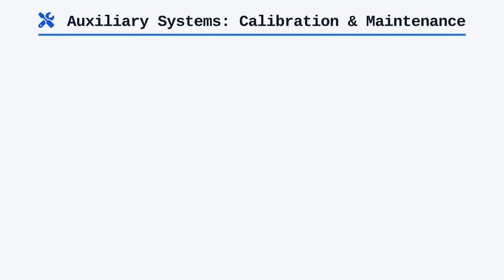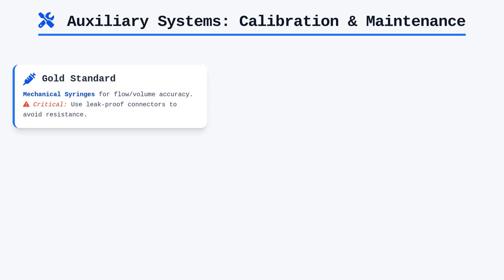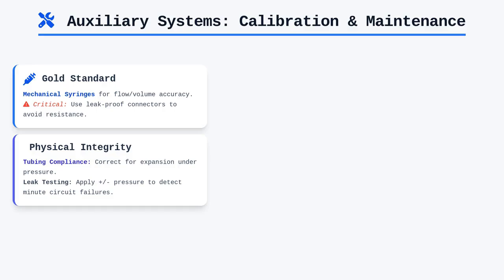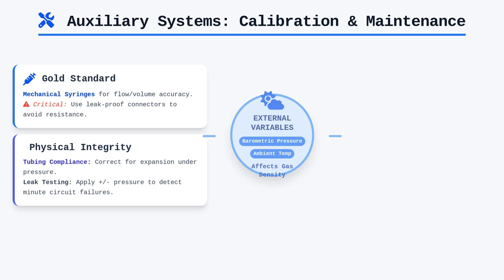Calibration and maintenance of these auxiliary systems are just as critical as the hardware used for patient maneuvers. Mechanical calibration syringes serve as the gold standard for verifying flow and volume accuracy, yet we must ensure they are used with appropriate connectors that do not introduce leaks or unintended resistance. When dealing with complex piping arrays, we are often forced to deal with the inherent compliance of the tubing, which expands under pressure and can lead to systematic errors if not corrected within the software's configuration. We must be diligent in performing regular mechanical integrity testing, which involves applying positive or negative pressure to a closed circuit to detect minute leaks that might only manifest under specific flow conditions.